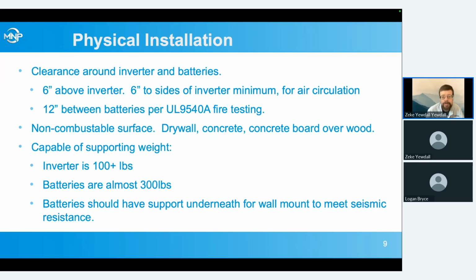Physical installation. We want to think about clearance around our inverters and batteries. Obviously, we've got code clearance of needing 3 foot in front of them for access and proper height of the location. We also want to think about ventilation, especially of the inverter. Batteries, ventilation is less of a concern, but the inverter, it's putting off a bunch of heat when it's operating. It's pulling in air from kind of behind the wiring compartment, and it needs 6 inches on the sides to be able to pull that air in. And then it needs 6 inches above the inverter, preferably a little more, but minimum 6, to let that hot air out. If you've got a whole bank of inverters, say you're doing a multi-stack, you're going to be putting off more heat, so maybe a little more room would be better.